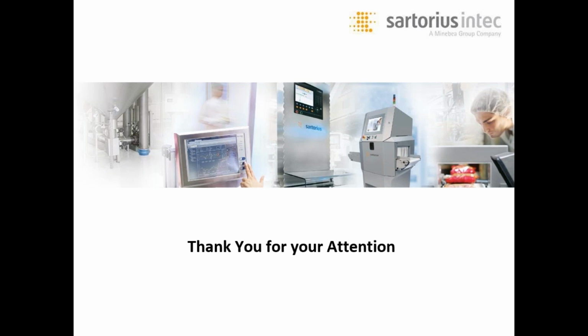Well, there are 2 questions there, just so you know. Is it necessary? No, it's not necessary by Sartorius' standards. But each facility, each customer is going to have their own standard operating procedure, and if that procedure requires them to calibrate it, then we do not override that. But to have an accurate system, we do not need to be calibrated. It's completely up to the customer if their procedure requires it.